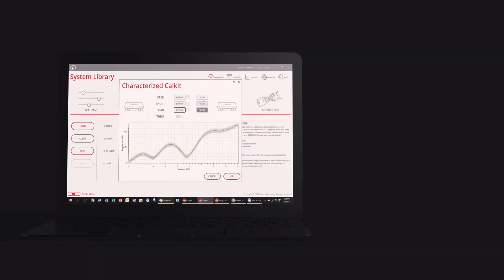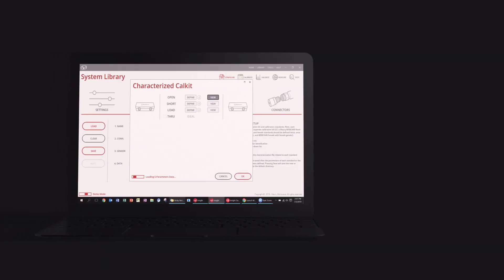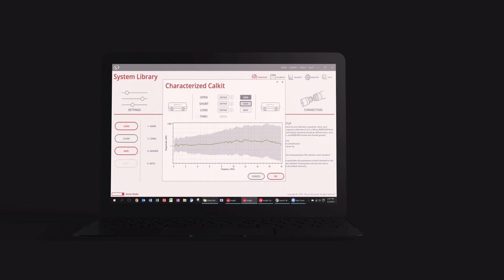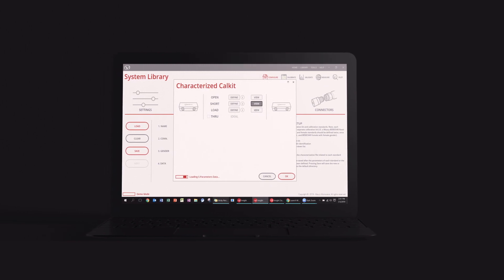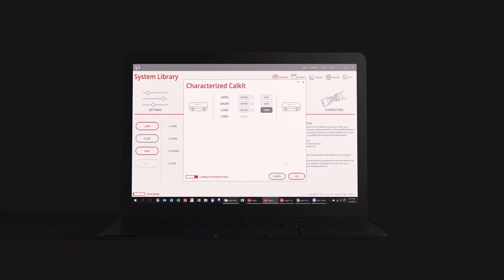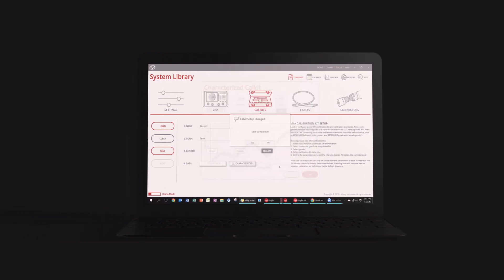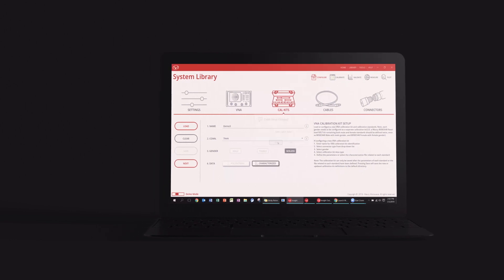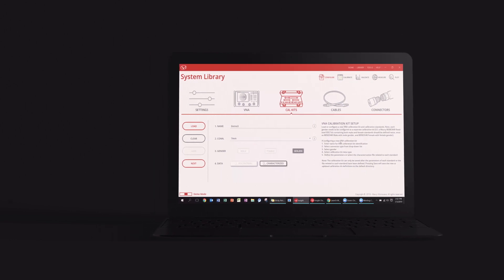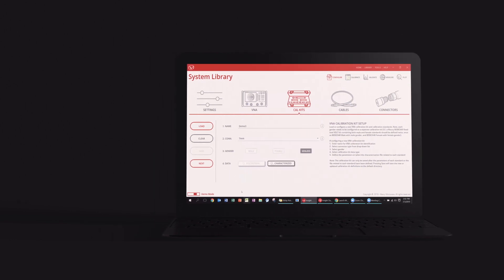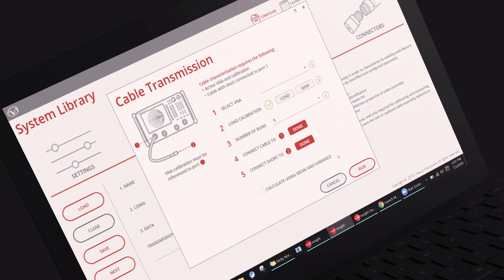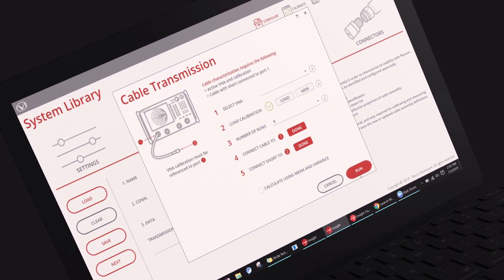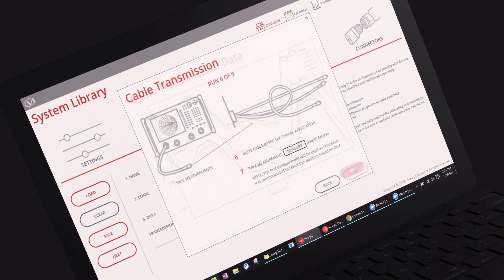VNA calibration kit uncertainties can be loaded if provided by the cal kit manufacturer. Mori's characterized device cal kits, model CK50 and CK51, include uncertainty data for each calibration standard.